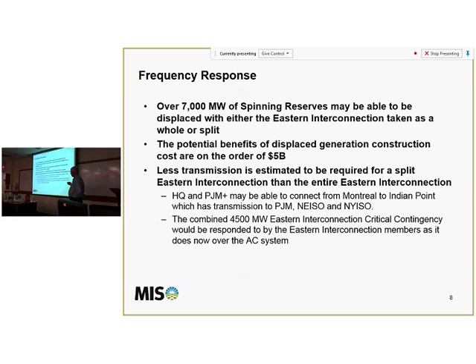Why now and not before? They didn't have voltage source converters that were big enough, and they didn't have DC breakers. Well, you can make a DC network that operates much like an AC network for frequency response and other products, and have it contingent—so if you lose one element, it would automatically pick up the schedule of the others.